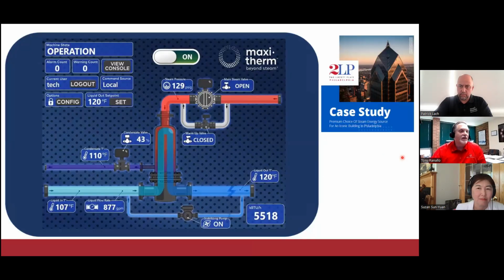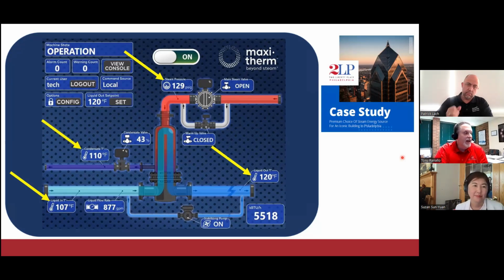Let's take a look at the screen. This is actually a screenshot from the unit in operation. What you'll see here at 2 Liberty is we're bringing in 129 pound steam, uncontrolled. We have a liquid outlet temperature of 120, which is at set point, so we're maintaining that. We have a return water temperature from the building at 107 degrees F, and our condensate is going out at 110. That's a 3-degree approach temperature.